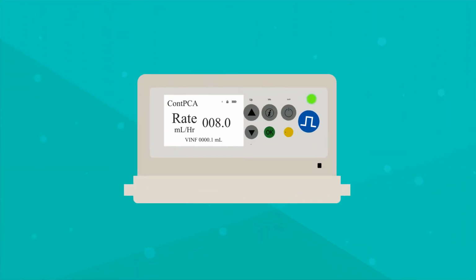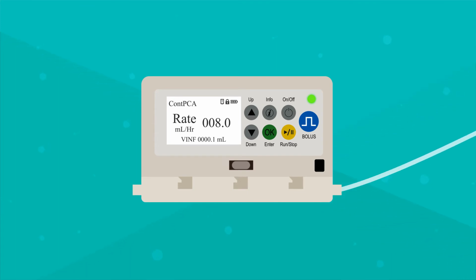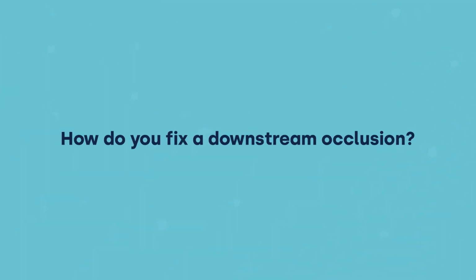It's possible you might see this happen when the pump is delivering a bolus, where it is infusing a higher dose of medication as rapidly as possible, causing a slight pressure buildup. Allow time for the medication to be absorbed. You do not need to take any action as long as the pump is not sounding an audible alert. Even if you see the pump stop and restart more than once, if you see the LED light turn back to green, it's a sign the pump is able to work through the situation on its own. If the pump does start beeping, then it has been stopped longer than 15 minutes and it needs help to overcome the blockage. How do you fix a downstream occlusion?